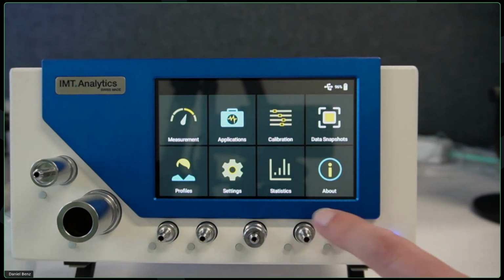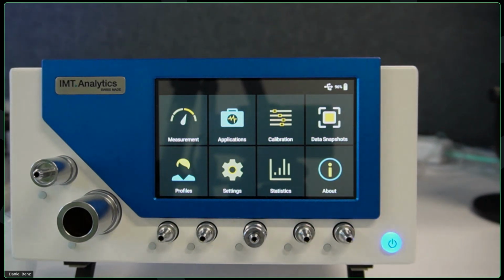Let's start on the right side here. This is our differential pressure measurement ports with a range of plus or minus 250 millibar or centimeters of water. Then in the middle here we have a combined port for high pressure and vacuum. So you can measure negative 14.5 psi to positive 145 psi. That means you can measure anything from vacuum pressure up to hospital line pressure. Then the last two ports here on the left side are our low differential pressure ports with a range of plus minus 10 millibar and an even higher accuracy in this measurement range.